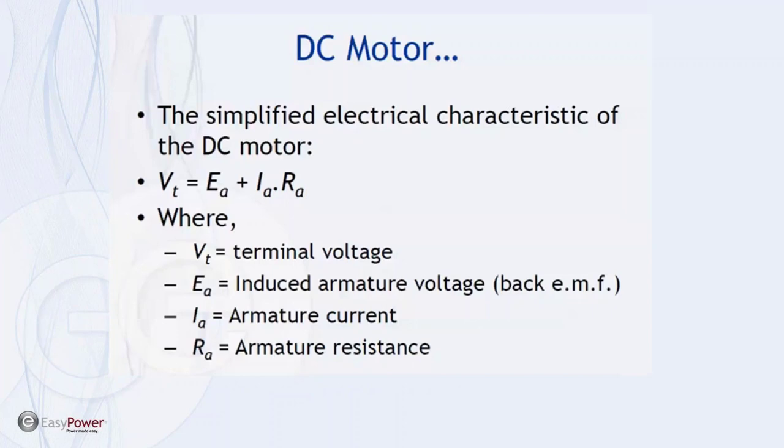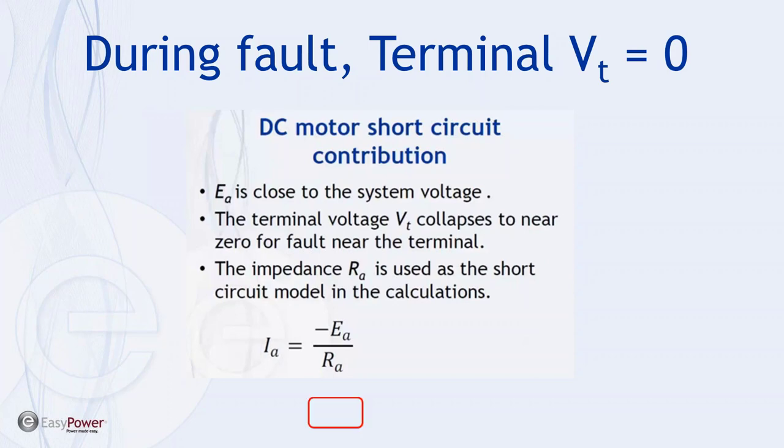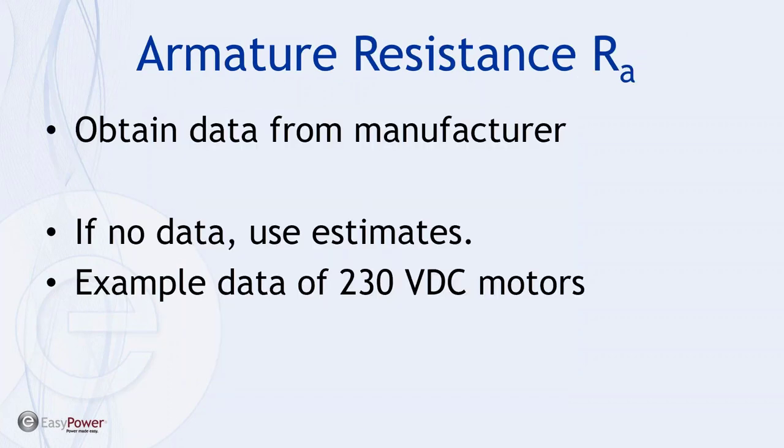Simplified electrical characteristics of the DC motor is effectively dependent upon the armature current, armature resistance, and the induced armature voltage or back EMF, which will add up to be the terminal voltage. So during a fault, the DC motor short circuit contribution ends up being dependent upon the equation here, which we're showing current equal the system voltage divided by the impedance of the resistor, of the armature.